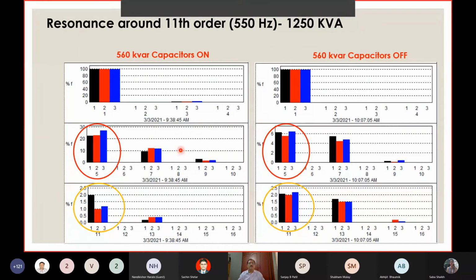So as you can see here, this is another site, 560 kVAr capacitors on. You will notice that the 11th order harmonic, see your 5th order harmonic is very high because of the 6 pulse drive. 7 is less than 5th order. 9 is even less, triple harmonic. But the 11th order picks up. In these two slides you can see here, capacitor on, capacitor off. So it basically means that the amplification takes place here. The resonance takes place at the 11th order, which is the normal observation when it comes to capacitors.